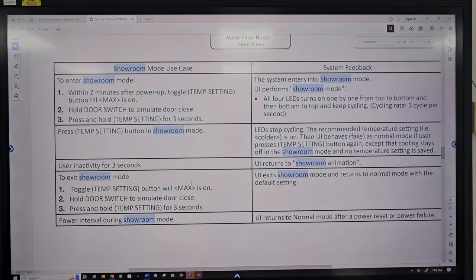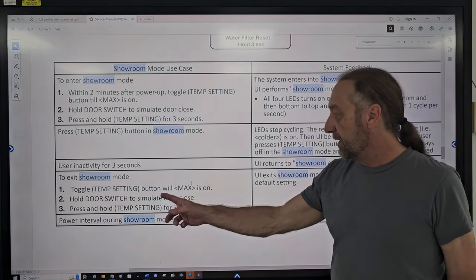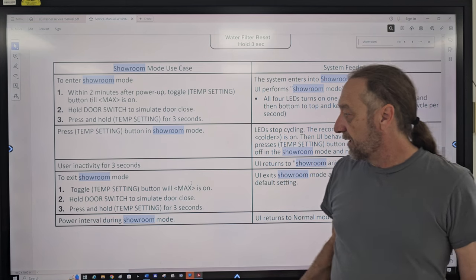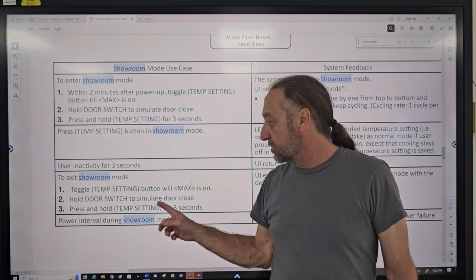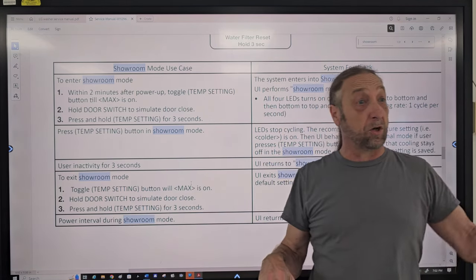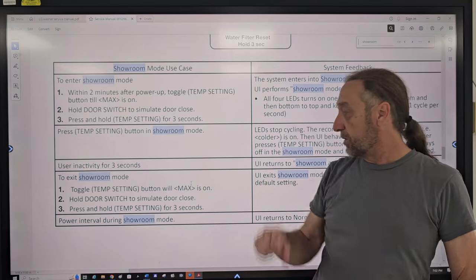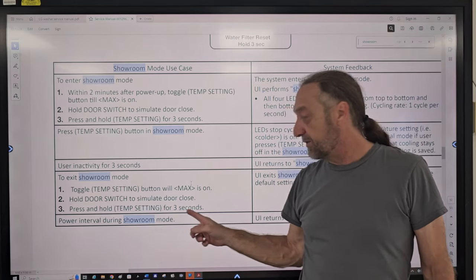To exit showroom mode, toggle the temperature set button with max on. Hold the door switch to simulate the door closed. So they want you to open the door and hold the door closed, and press and hold temp setting for 3 seconds.